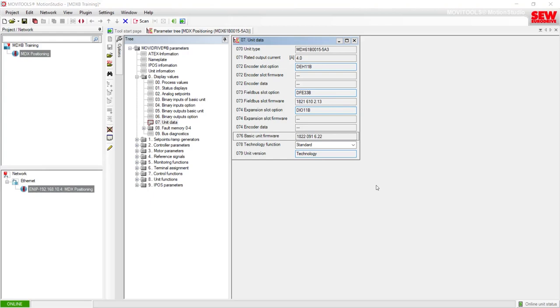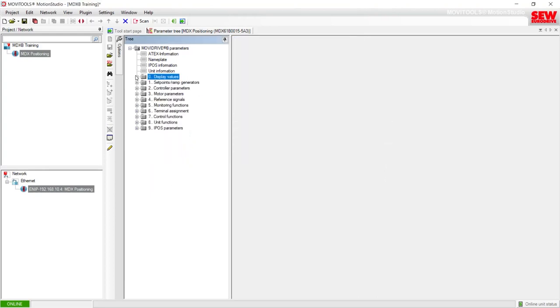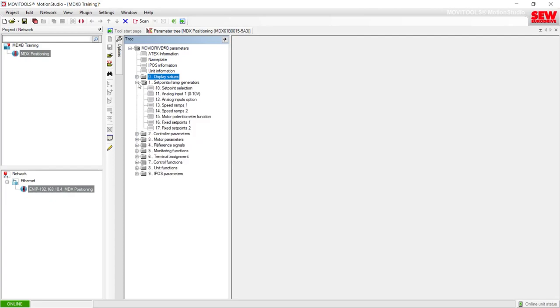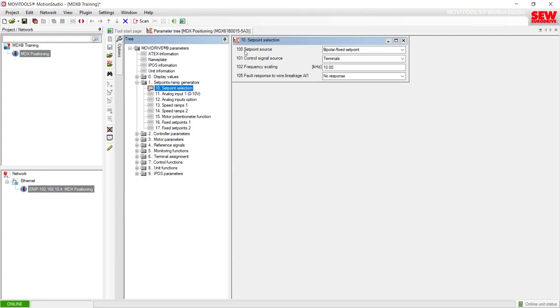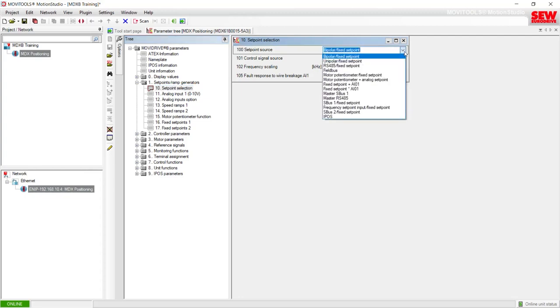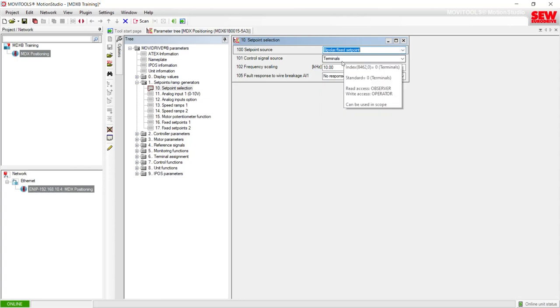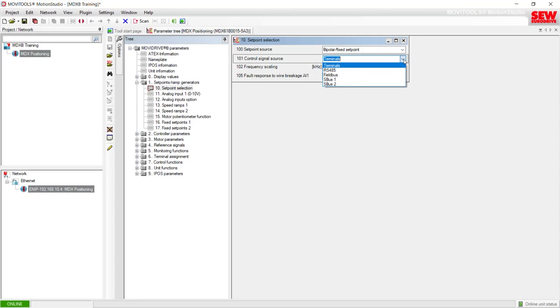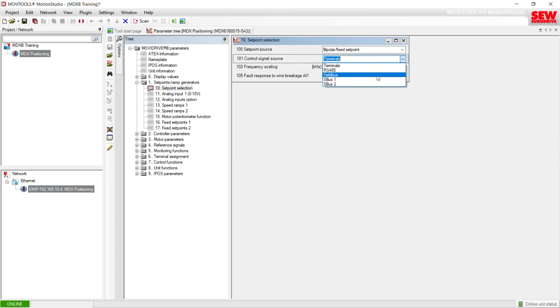The next questions talk about folder group number one, Set Points and Ramp Generators. In item 10, Set Point Selection, parameter 100 is where we tell the MOVIDRIVE where it should look for its set points — these can be fixed parameter values, field bus values, or other listed options. Parameter 101 is the control signal source: do you want the MOVIDRIVE to respond from the terminals, from the field bus, or from another supported network?